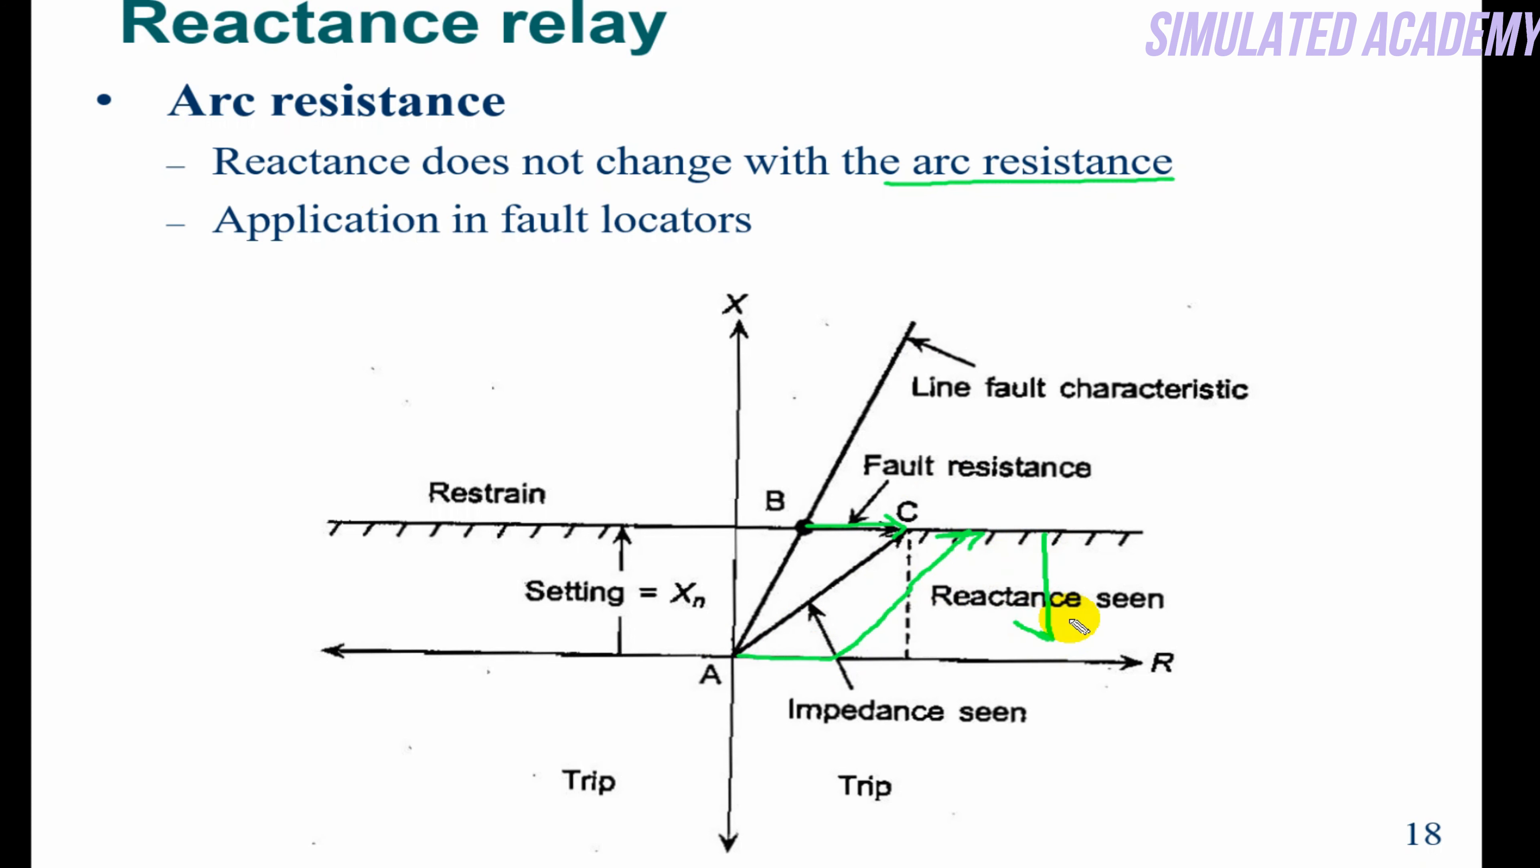If we plot this line, it will still be under this region, so it will operate. This means arc resistance does not change the reactance—reactance doesn't change with arc resistance. So its application is in fault location.